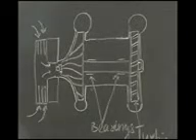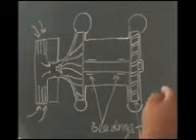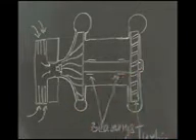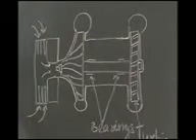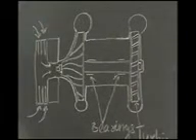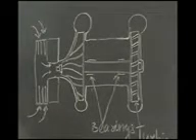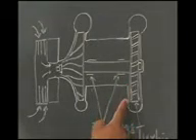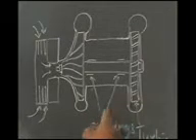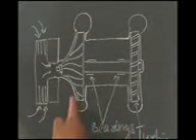And when we push it from this side from the turbine side, turbine end, then also the axial play should not exceed the limits described in the manual. That means if the limit is more, that means either the turbine blades are touching the casing, or the compressor blades are touching the casing.